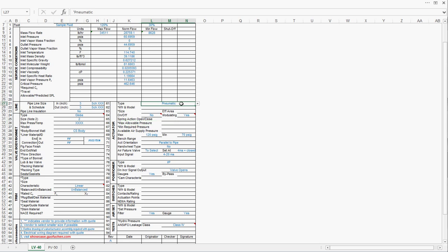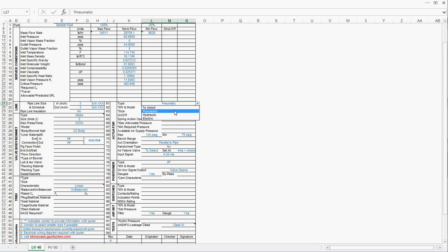Actuator. Three kinds: Pneumatic, hydraulic, and electrical. Pneumatic uses instrument air to drive the actuator, while hydraulic is using a liquid, most likely some sort of oil. An electrical actuator is using a motor. Most of the time it's pneumatic.